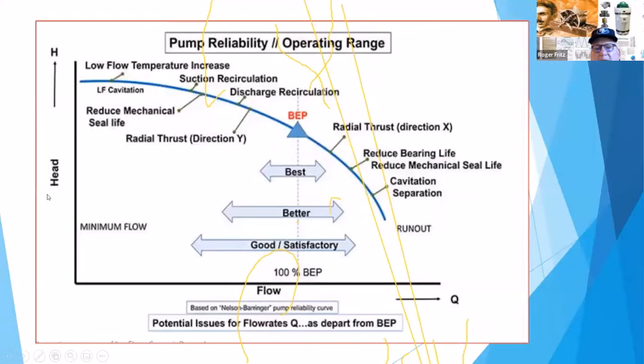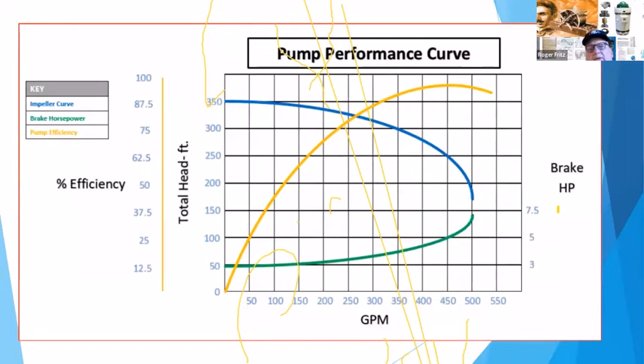The other area on pumping application that I want to talk about is it's very important to understand pump curves and where is the optimal sweet spot of those motors and pumps that want to work together, that are optimal horsepower with the optimal lift or head feet that we're going against. And then, this is the brake horsepower, this is the total feet of head. And then this is where the impeller is turned and cut to for that given speed that gives its best performance.